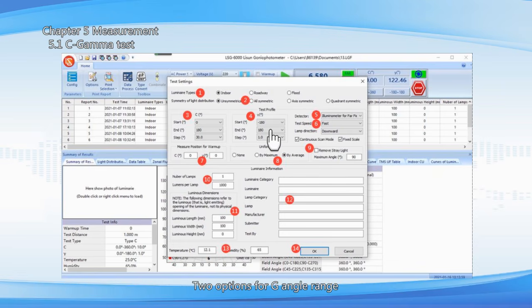2 options for the G angle range. -180 to 180 is for samples with lighting angles bigger than 180 degrees. -90 to 90 is for samples with smaller lighting angles. Always choose one for the G step angle. Select the detector. In most cases, you need to use the far field photo detector. You only need to use the near field photo detector for samples with very weak light. Select the test speed. Usually just use normal.